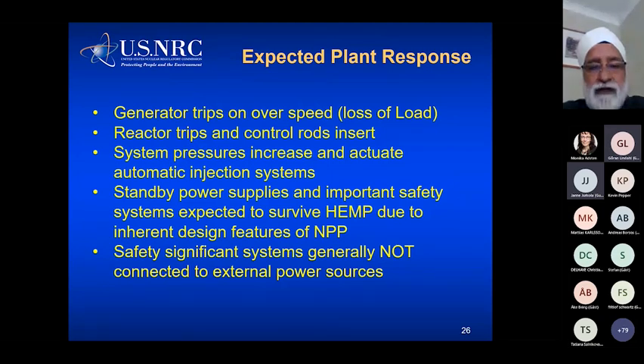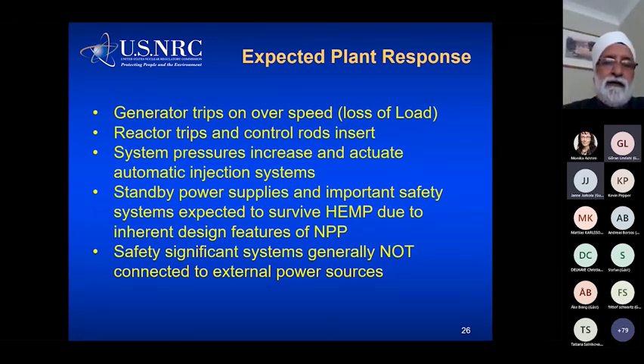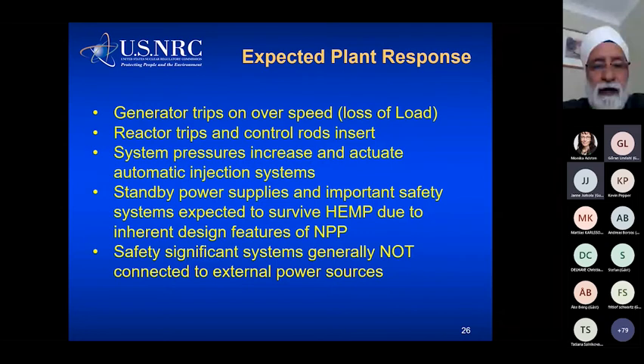We feel the diesel generators will start and run because they were not connected to the electrical power system before the event. And again, most of the safety systems are not connected to the external power sources. And that's important because the E3 wave, which travels through the conductors, through the offsite sources, through the transformers, can carry into the plant and can damage equipment that's connected. But most of the standby systems that are required for safely shutting down the plant are not connected electrically.